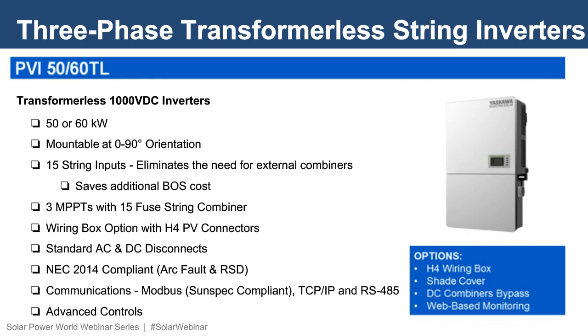The PVI 50 and 60 TL are Solectria's newest offering of three-phase transformerless string inverters. These units are 1,000-volt DC inverters, in 50 or 60 kilowatt power classes with a 480-volt AC output. These inverters have 3 MPPT input channels, each with 5 string inputs apiece. The integrated combiner box allows for up to 15 string inputs from the array, eliminating the need for an external combiner box. This is significant savings on your installed BOS costs. The 3 MPPT trackers also allow you to harvest the maximum energy yield from the array and give you flexibility in the array design and installation, allowing for varying string lengths, different module types, or even different array orientations.